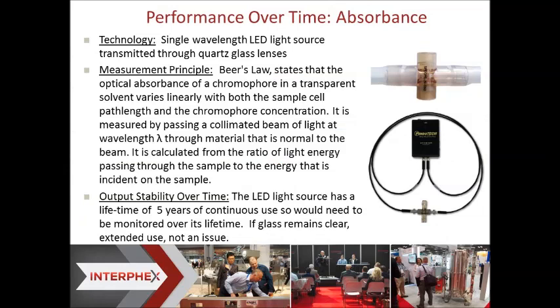As far as absorbance measurement, we use a photometer, which is a single wavelength light source. And it's transmitted through our sensor, which has quartz glass embedded into the wall on both sides. So the light source and detector shines across. And the light that's not absorbed by the sample cell as liquid flows through it is measured by the detector. And the important thing with this, per Beer's law, is the path length. And we have a well-defined path length due to the fact our sensors are molded parts.